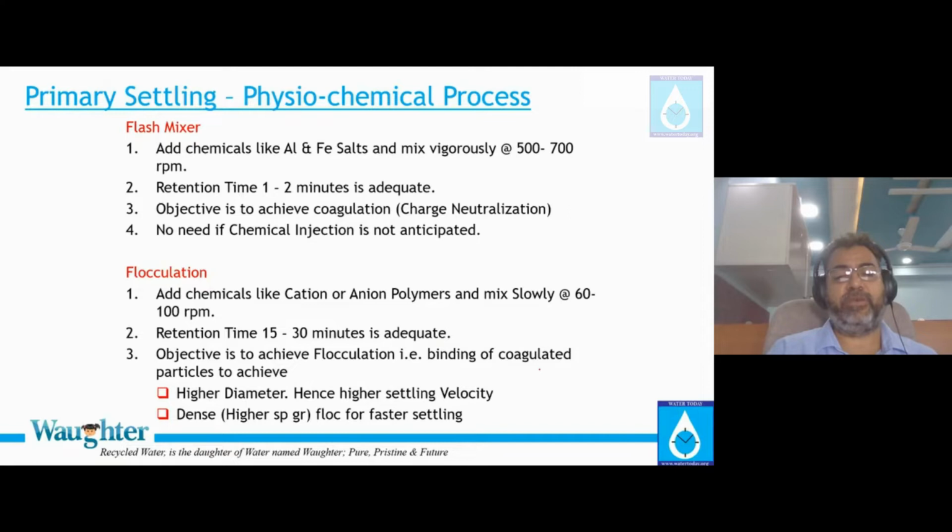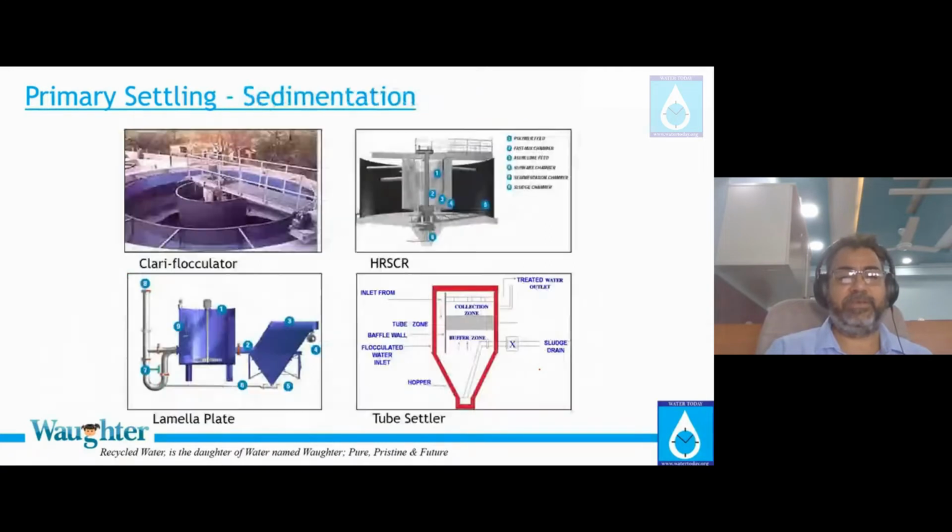The result of a flocculation trial is not only diameter. If you increase the diameter, but your flock is not dense, but something called a fluffy flock, would you like it? The answer is no, because with fluffy flock the specific gravity will go down. So when you do a flocculation experiment, focus on the increase in the particle size as well as making the flock dense.